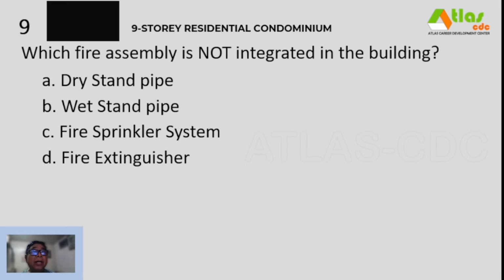Number 9, for a 9-story residential condominium, which fire assembly is not integrated in the building? A. Dry standpipe. B. Wet standpipe. C. Fire sprinkler system. And D. Fire extinguisher.